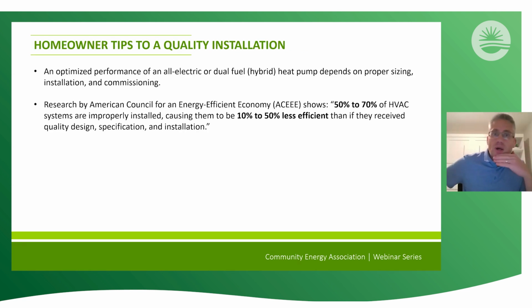Getting into the homeowner tips to a quality installation. This is actually a business philosophy of ours, because we do design systems as well: looking at it not from the box itself, but at the process, the steps and the sequencing to deliver optimized performance. Simply expecting the equipment to operate like a refrigerator, where you plug it in and it works to what it says on the rating plate, doesn't work that way when it comes to space heating and cooling systems. It depends on making sure the system is properly sized and installed to acceptable standards of practice. And one of the most overlooked components is the performance verification and the commissioning of a system.